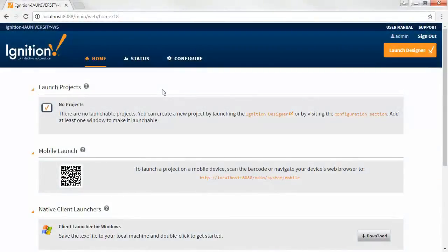In this video, we're going to be talking about tags. Tags in Ignition are points of data that have static or dynamic values. The values can come from OPC addresses, such as from a PLC, a SQL query, an expression or a calculation, and many more. Tags in Ignition are very important because Ignition uses them to configure real-time control screens, set up alarming on the tags, and store history on their values.